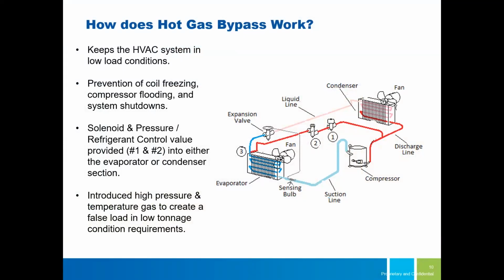So hot gas bypass. Let's give you a super high level diagram of how it works. You can see that there's a dedicated line off the discharge side of the compressor that tees off and runs over into the evaporator. You have a solenoid valve and a pressure valve there that can make sure that the hot gas can run to either your condenser or the evaporator based on your conditions. The idea is that you're introducing hot gas and bypassing it around the condenser and sending it straight into the evaporator. And what happens in this kind of application, and this terminology is really good, is I call it false load.